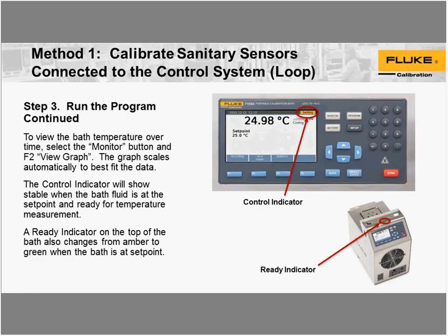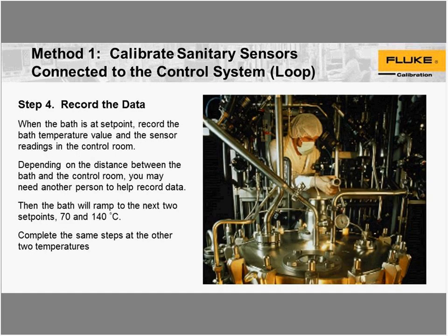Once it arrives at the set point and settles in, the light on the top of the unit will turn on. It's called the indicator. It'll change from amber to green to let you know that it's stable enough to take data. After that, you just record the data that you need, whether it's data from a control room or from the 1586.